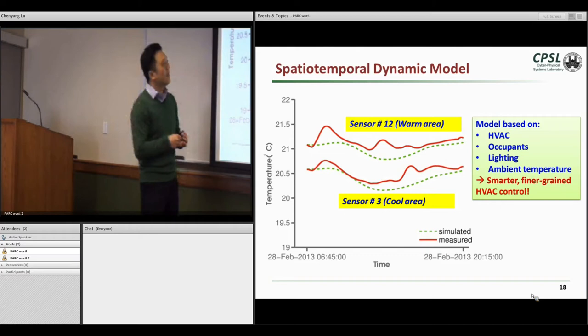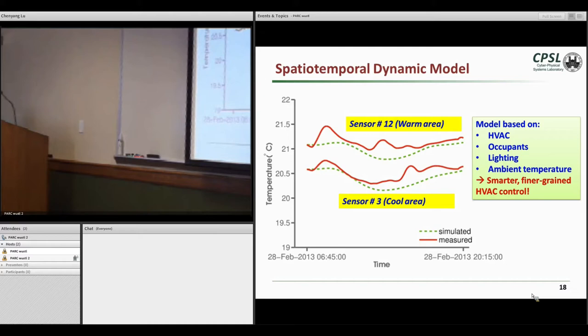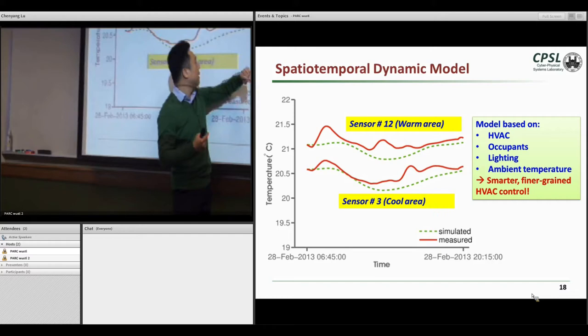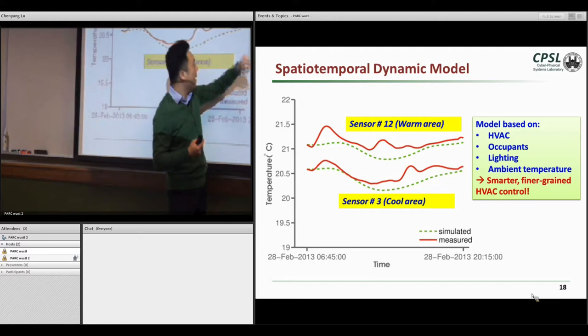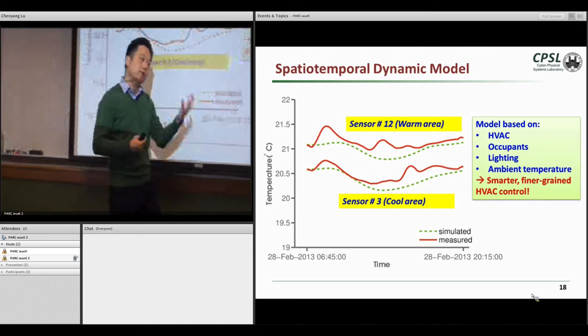It takes into account whether the HVAC is working, what the airflow is, where the occupants are, and whether the lighting is on, because lighting actually generates a fair amount of heat load, plus the ambient temperature from outside. Based on that real data set, we drive the estimation of the parameters.